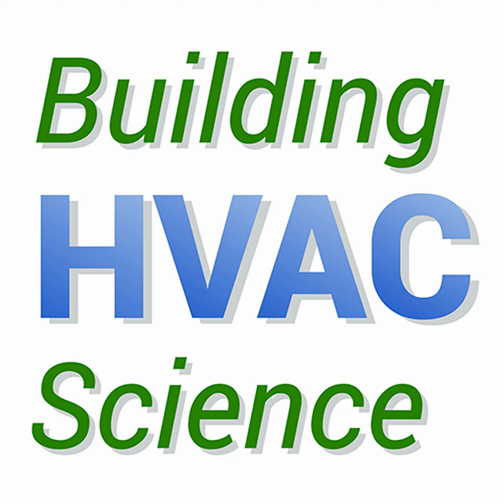We go above and beyond with startup—standard tests like making sure fans run in the right direction, all your standard test points. We actually run the unit for a couple of days to make sure that across a range of conditions, it's meeting those specifications. So startup is straightforward.